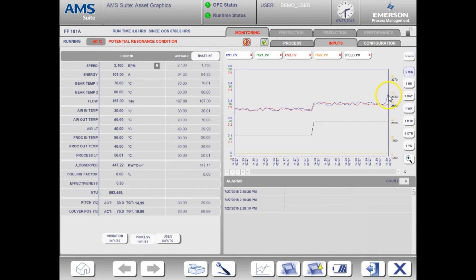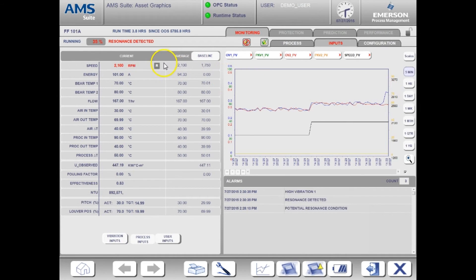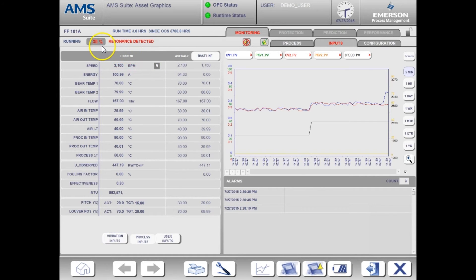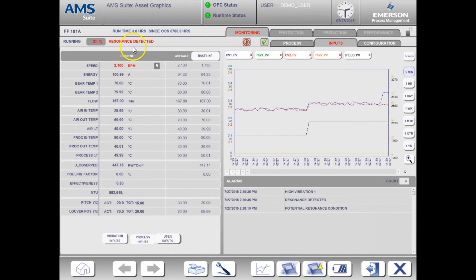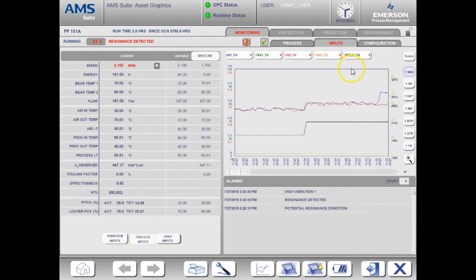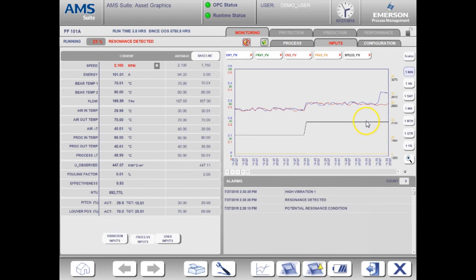Look at the health value and alarm. We are showing 35% health and a critical alert for resonance detected. In this case, we are looking at multiple parameters to determine the fault condition. Now that we have high vibration and are operating at a known resonance speed, the severity and confidence level of the fault have increased.